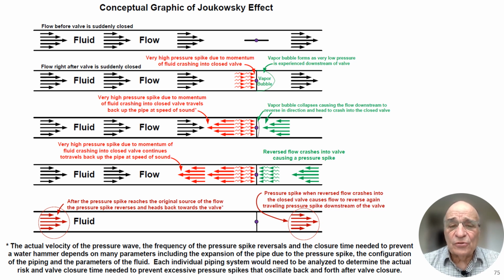That's not the end of the story. The Joukowsky effect then sends a pressure wave at the same spiked pressure all the way back to the source of where the LNG was coming from. So let's say this pressure spike was 1,000 psi. Well, that 1,000 psi spike, even though this may be operating at 200 psi, travels all the way back to the source of where the LNG was coming from.